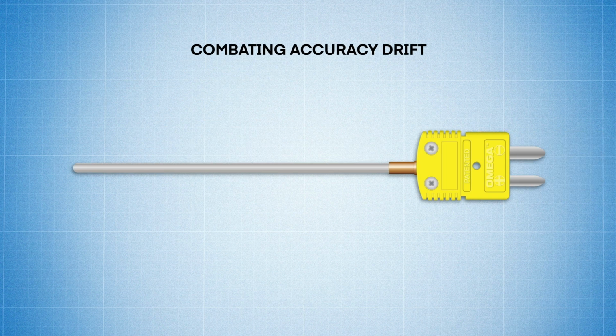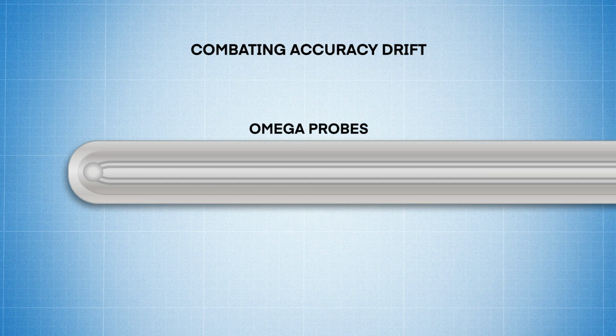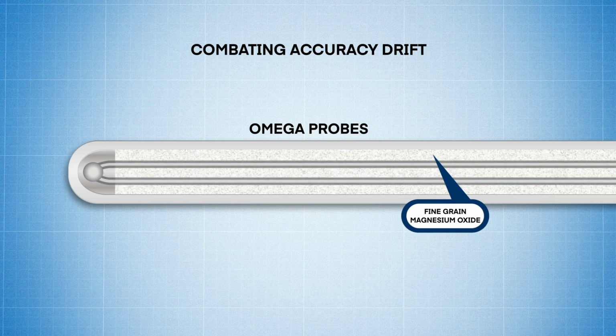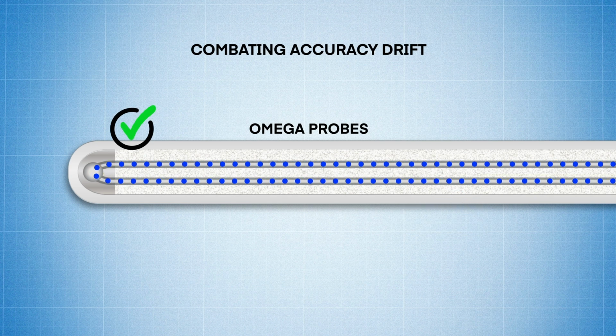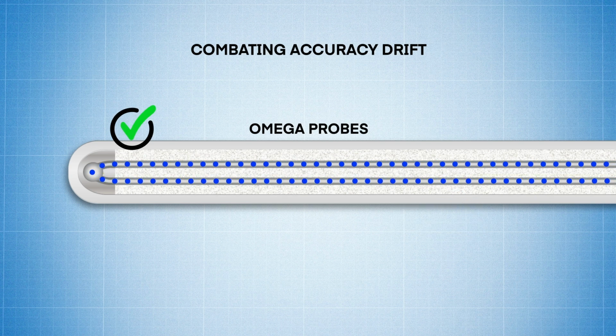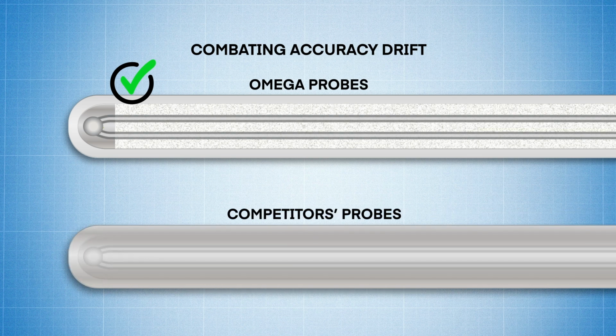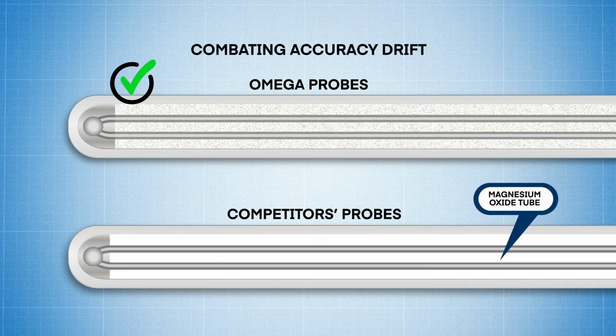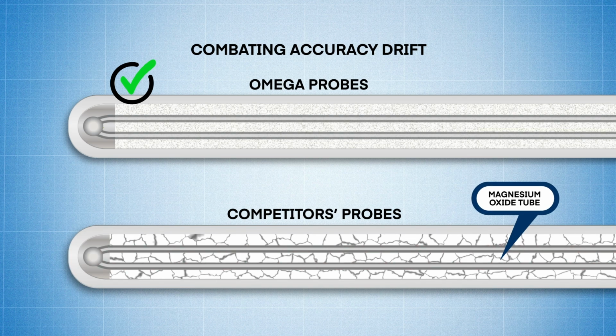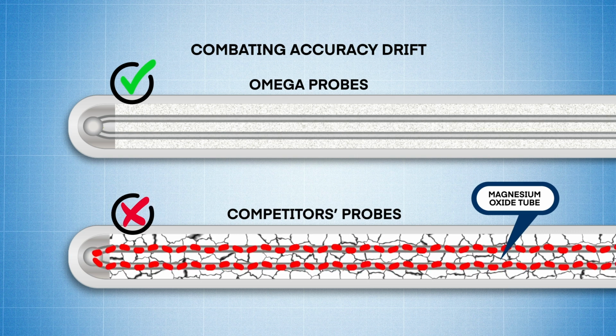To combat accuracy drift, DwyerOmega only uses a fine-grained, high-purity magnesium oxide insulation, resulting in less stress on the thermocouple alloy wires during assembly, while our competitor's insulation starts as a rigid, pre-formed magnesium oxide tube that is crushed during the manufacturing process, putting much more stress on the alloy wires.